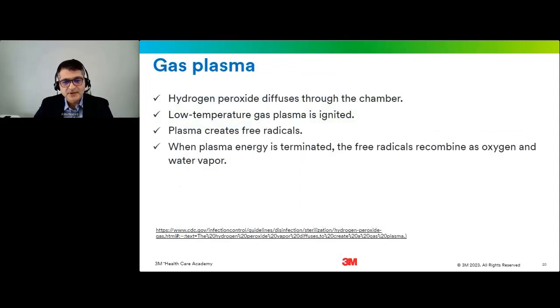So I mentioned gas plasma. How does a gas plasma system work? Plasma is the fourth state of matter. Plasma is a gas-like substance consisting of particles such as positive and negative ions and electrons. Once hydrogen peroxide diffuses through the chamber and surrounds the instrument, low-temperature gas plasma is ignited by applying an electric field, and plasma causes the hydrogen peroxide vapor to break into free radicals. When plasma energy is terminated, the free radicals lose their energy state and they can recombine. And when they recombine, oxygen and water vapor are produced.